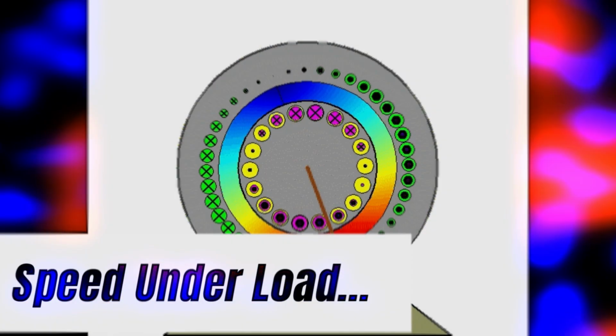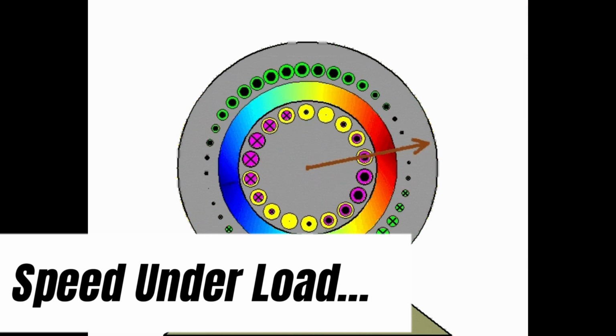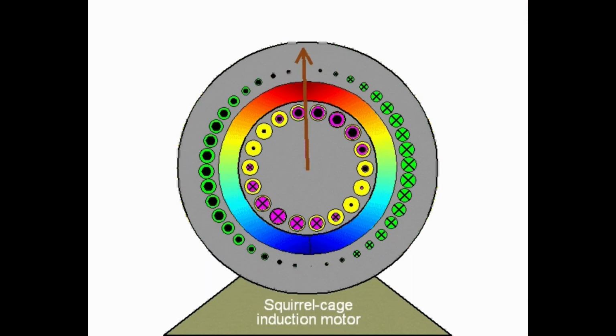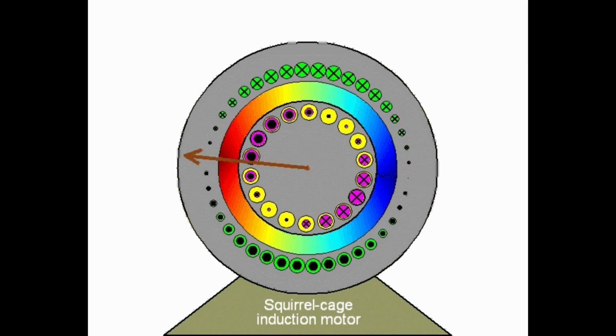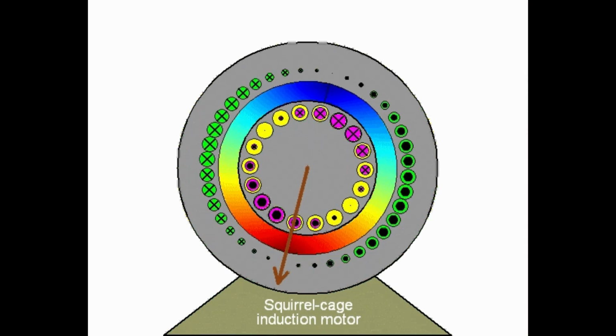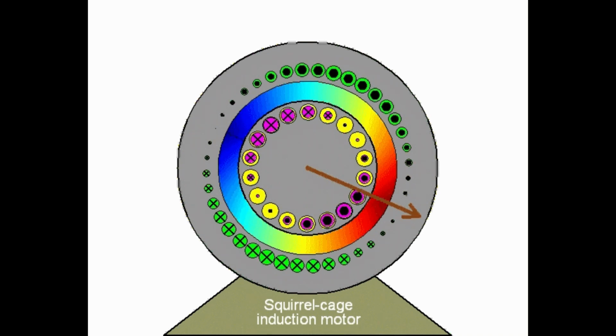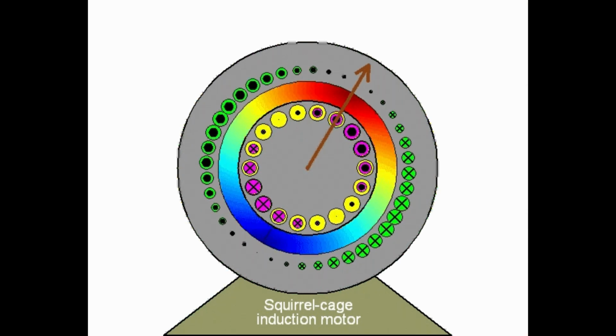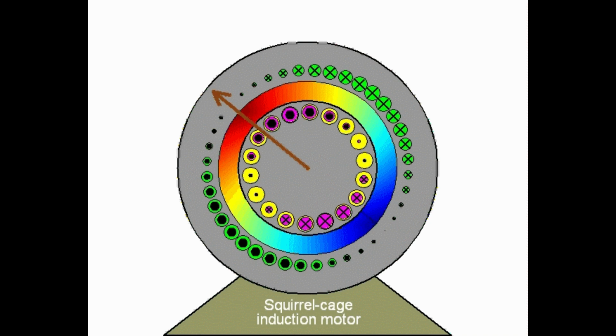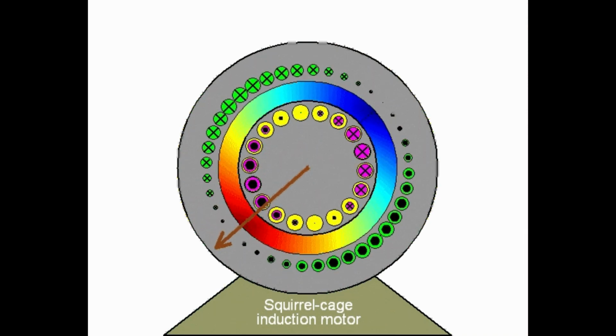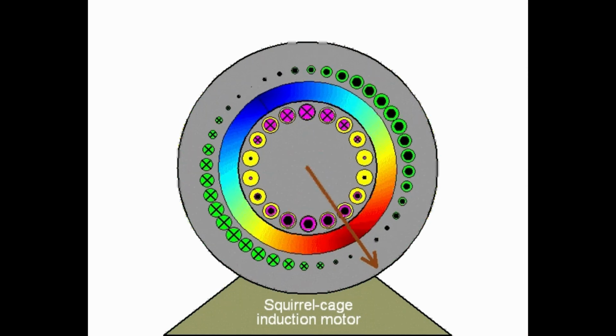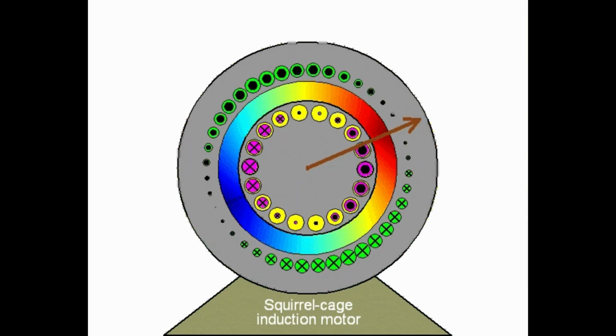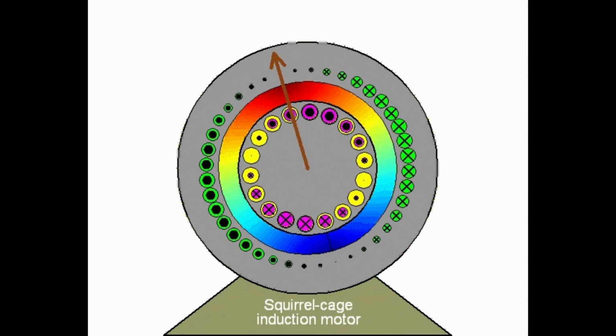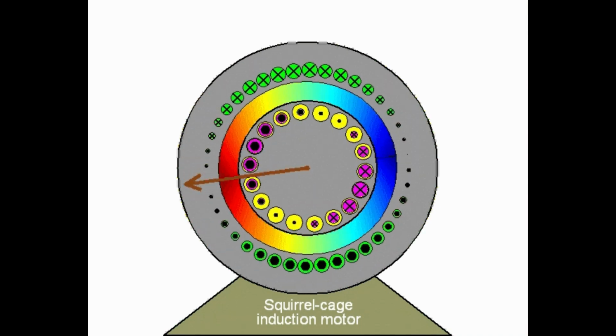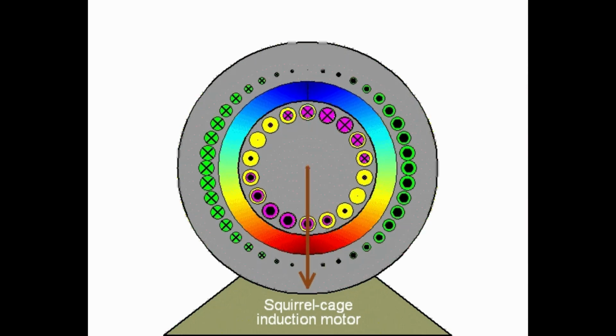Speed under load. As the rotor slows down under the load, the speed adjusts itself to the point where the forces exerted by the magnetic field on the rotor are sufficient to overcome the torque required by the load. Slip is the term given to the difference between the speed of the magnetic field and the speed of the rotor.